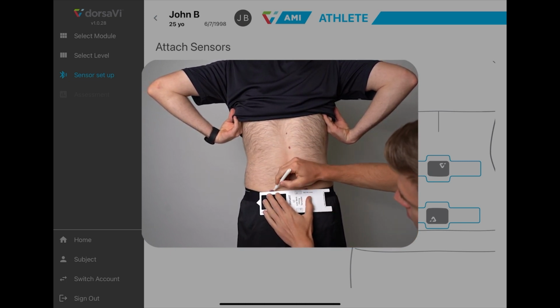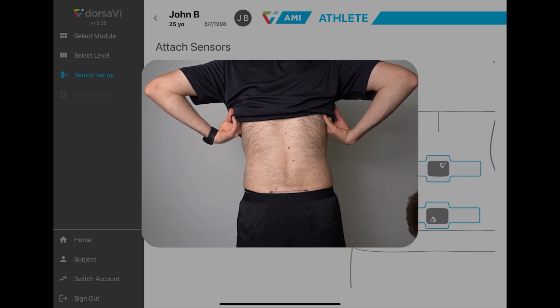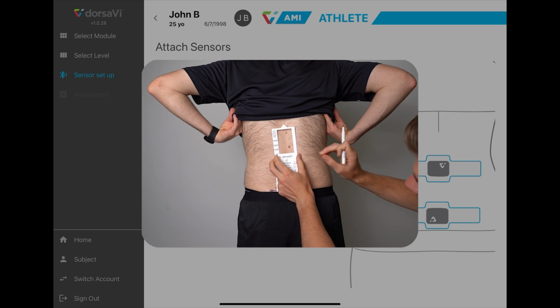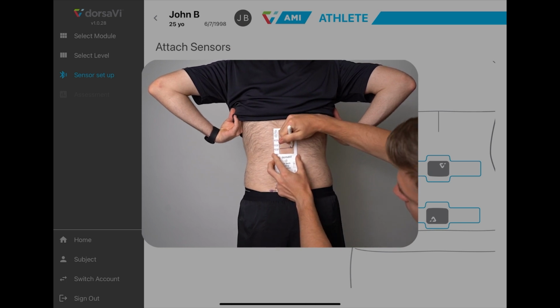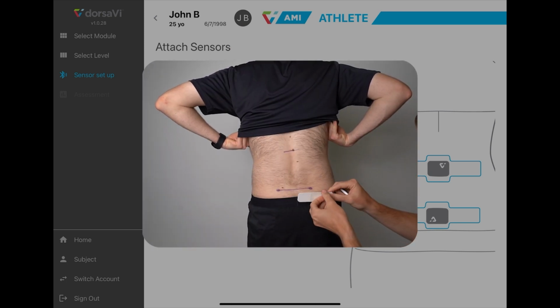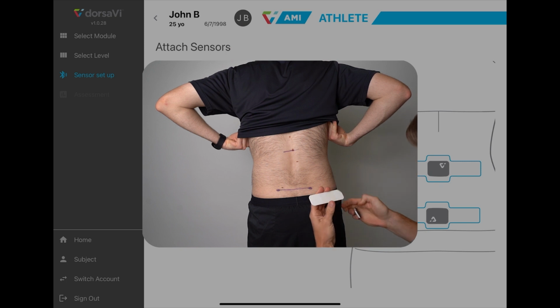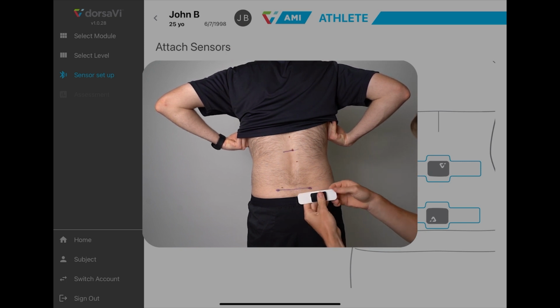Grab the green flashing sensor and place it on the low back adhesive. These adhesives are in the tube and they're the longer adhesives. Place the sensor below the line you drew with the green light flashing down. Your subject's line will intersect the middle of the sensor.